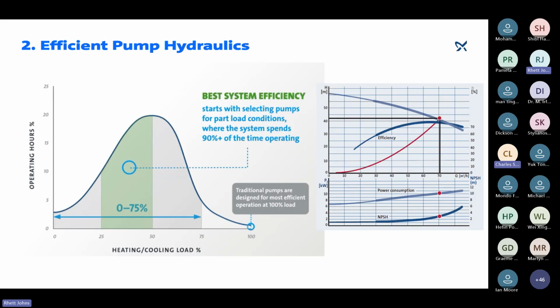Yep, and the efficient pump hydraulics. Another crucial aspect of system design is that we ensure that our hydraulic selections reflect the most common operating conditions of our system. So, for example, it's quite common for a pump supplier to select their pump so it's running its most efficient based on the max rated conditions of the system. And my background is actually working for a pump supplier, and I can say from experience that if we are just focusing on the supply of the pumps, that is very commonly the way that pumps get selected. However, the question we must ask is how long and how regularly will the system run at max conditions?